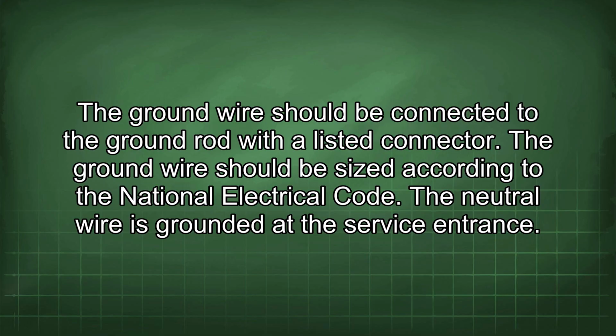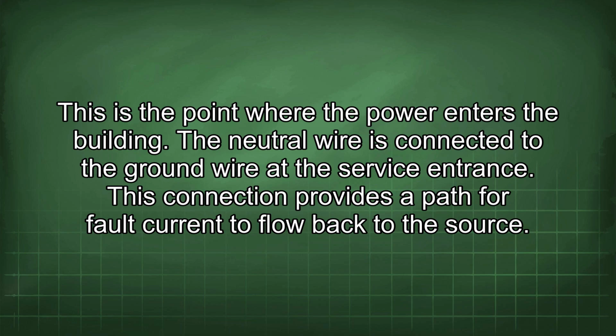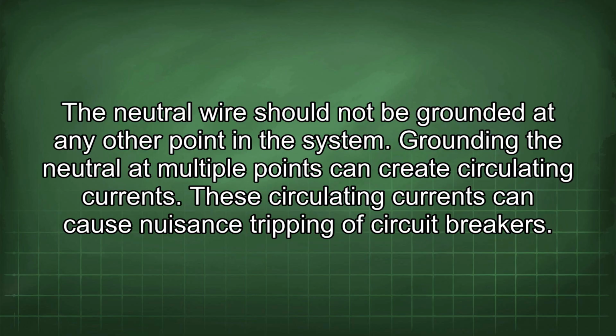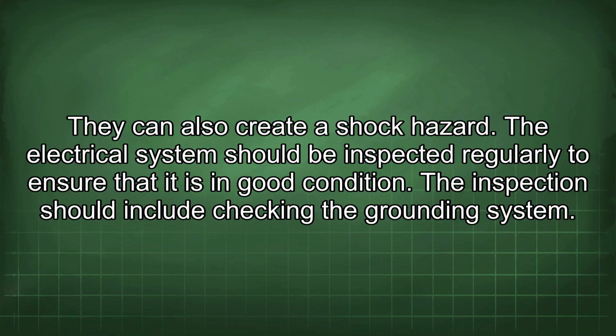The neutral wire is grounded at the service entrance. This is the point where the power enters the building. The neutral wire is connected to the ground wire at the service entrance. This connection provides a path for fault current to flow back to the source. The neutral wire should not be grounded at any other point in the system. Grounding the neutral at multiple points can create circulating currents. These circulating currents can cause nuisance tripping of circuit breakers. They can also create a shock hazard.